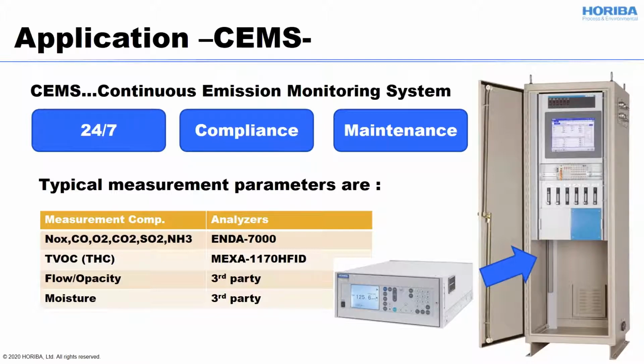All of the CEMS users have an air permit which describes the requirements, what to measure, such as NOx, SO2, CO, O2, moisture, flow, temperature, etc. Then some CEMS requirements include the total hydrocarbons. So for that purpose, MEXA-1170HFID can be used. By the way, HORIBA has the ENDA-7000 series, which was developed dedicated to CEMS applications. We can install MEXA-1170HFID into this rack to work with ENDA-7000, so that you can combine all of the measurement data to output together.